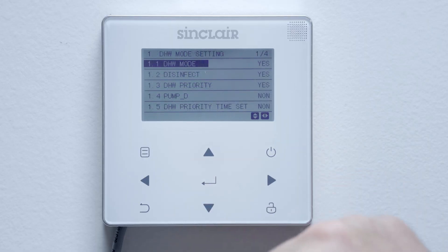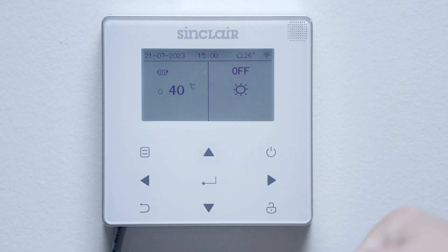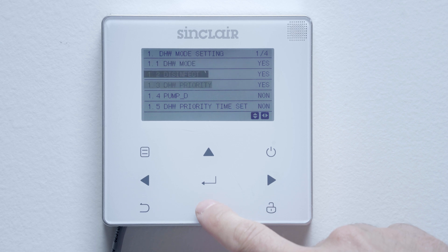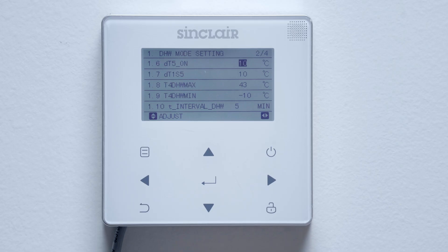If domestic hot water is not required, it is recommended to disable it. Select domestic hot water mode and then on the first line select option 'no.' Now the tap icon has disappeared from the main page — the domestic hot water mode is therefore deactivated. If the domestic hot water function is desired, leave the default settings. The default hysteresis DT5ON is 10 degrees. If the water temperature in the tank drops by this value below the target temperature, the heat pump starts preparing domestic hot water again. Here we recommend to use DT5ON of 5 degrees.